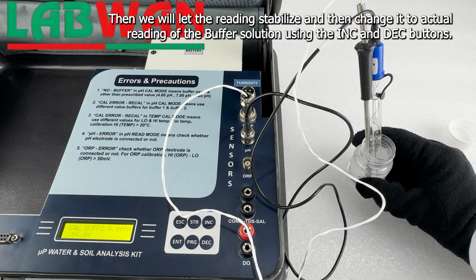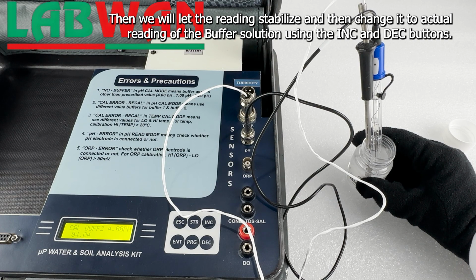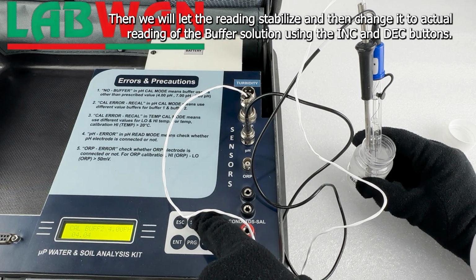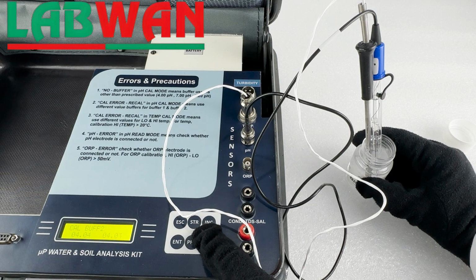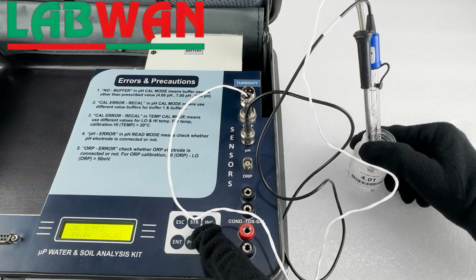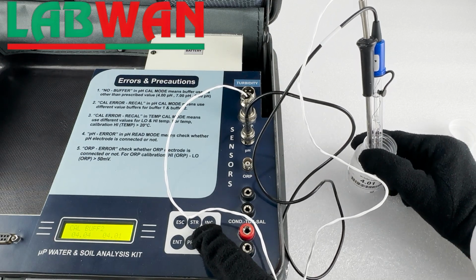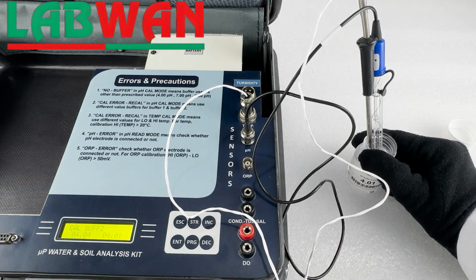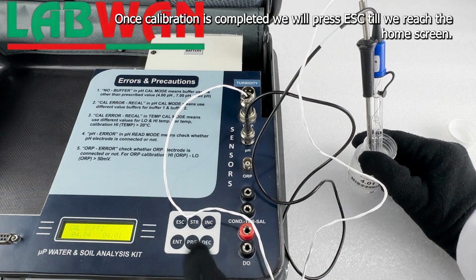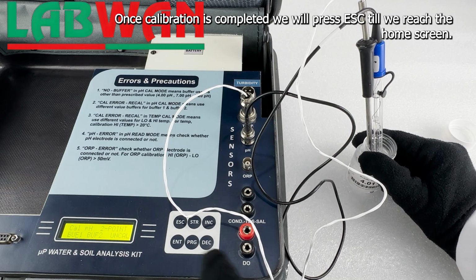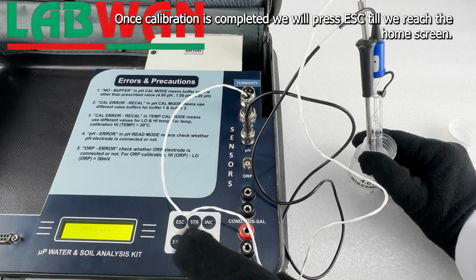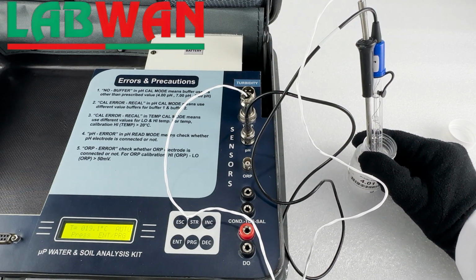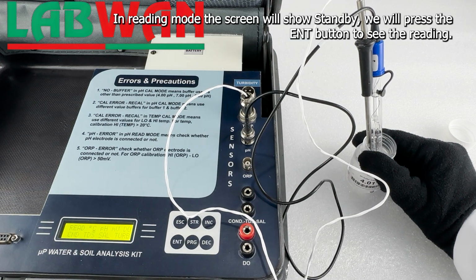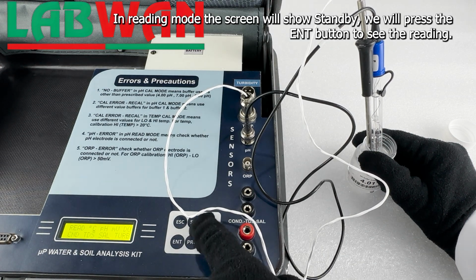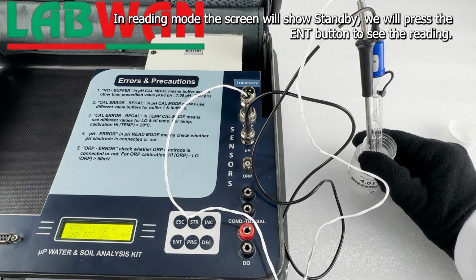Then we will let the reading stabilize, and then change it to actual reading of the buffer solution using the INC and DEC buttons. Once calibration is completed, we will press Escape till we reach the home screen. In reading mode, the screen will show standby. We will press the ENT button to see the reading.